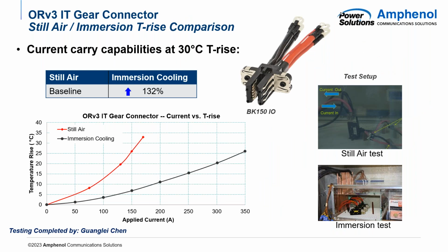In the beginning, I've also mentioned that we've done quite a bit of work with some of the immersion cooling committees within OCP. This has been done by our thermal team within our business unit. And we've conducted some immersion testing to compare against the baseline, which is the still air in the spec. And as you can see in the immersed cooling, the static cooling environment, we've seen quite a significant increase in power density, up to 132%, essentially doubling the current in an immersed test environment versus a still air test.